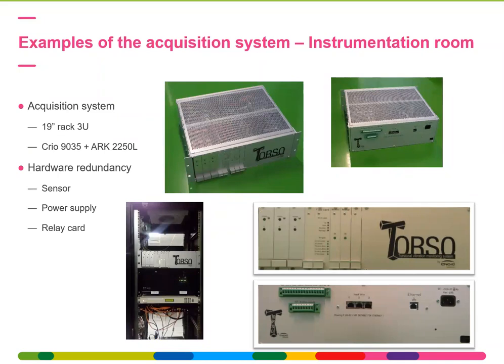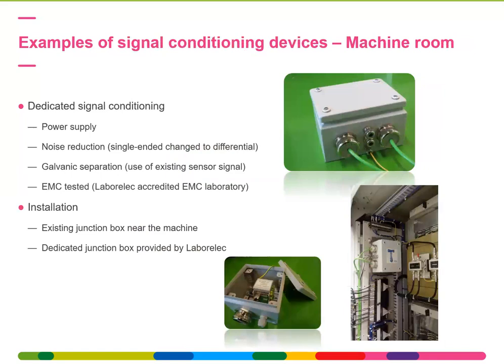So this is the system that you typically install in a cabinet, an existing one or a new one provided by Laborelec. Signal conditioning, again, is close to the sensor typically, or in the instrumentation room if an existing speed sensor can be used. The goal of the junction box is to have the power supply, signal conditioning, noise reduction, or galvanic separation when using the existing sensor. And of course it's EMC tested to ensure that any disturbance is not affecting the quality of the system.